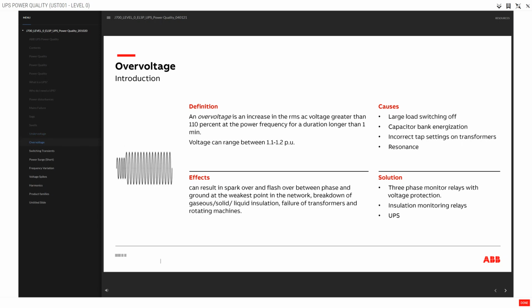Definition: an overvoltage is an increase in the RMS AC voltage greater than 110% at the power frequency for a duration longer than 1 minute. Voltage can range between 1.1 to 1.2 per unit. Causes: large load switching off, capacitor bank energization, incorrect tap settings on transformers, resonance. Effects: can result in spark over and flash over between phase and ground at the weakest point in the network, breakdown of gaseous/solid/liquid insulation, failure of transformers and rotating machines. Solution: three-phase monitor relays with voltage protection. Insulation monitoring relays. UPS.